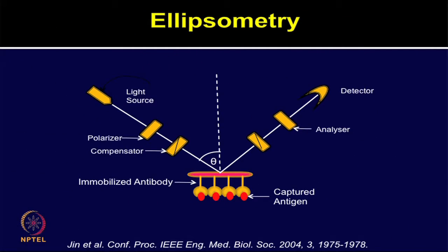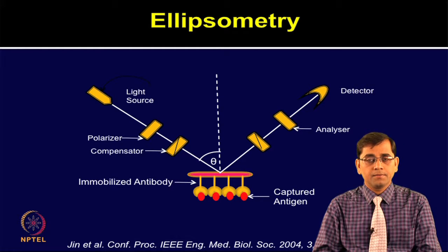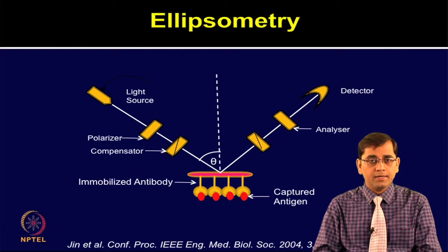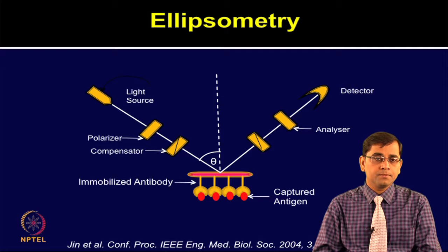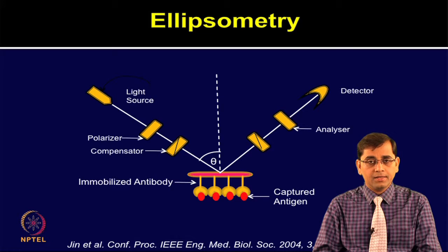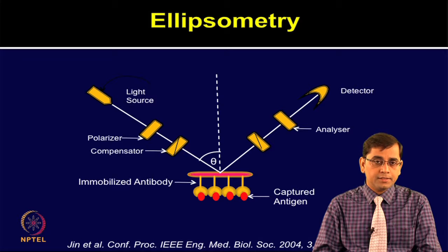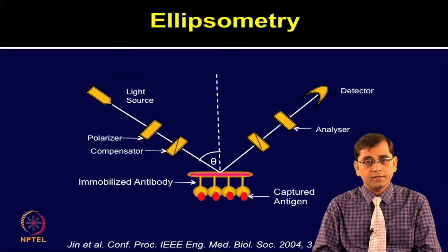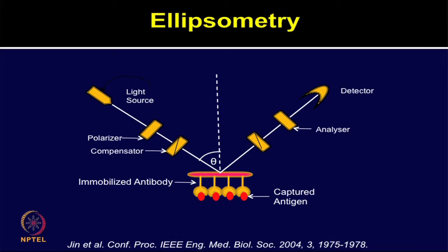In this slide, I have shown you a configuration for an ellipsometry-based label-free technique. A monochromatic laser light, linearly polarized by the polarizer, is passed through a compensator to produce elliptically polarized light. This light is reflected from the sample surface and again becomes linearly polarized, which is detected by an analyzer filter. The reflected light intensity is monitored with a photodetector.